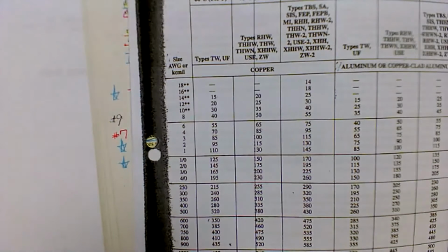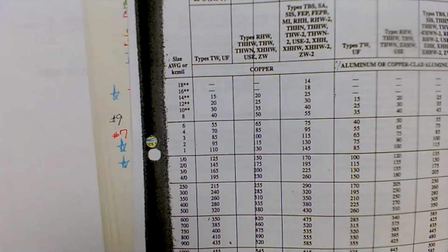Yep, they had it. It was not planned right. I think it was 6 strands of wire in there, and it had gotten so hot at the receptacle that it had turned the conduit discolored, about a foot from the receptacle. And we pulled the wires out. They hadn't breached each other yet, but they were melted together. That clear coating you're talking about on that THHN, it was all melted together.